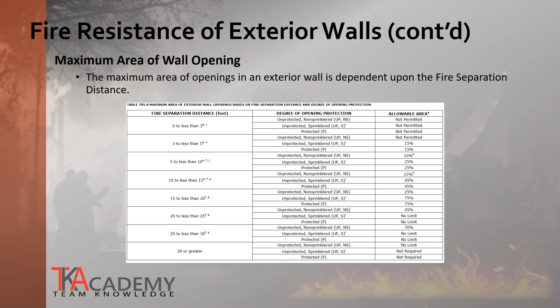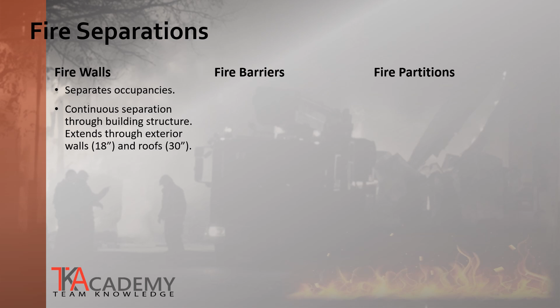Fire separations within a building are meant to contain a fire and keep it from spreading to other areas. Fire separations can be done with firewalls, fire barriers, and fire partitions. Firewalls are the most stringent, and they are used to separate occupancies. It is a continuous separation that extends through the building structure. Firewalls extend through exterior walls by 18 inches and through roofs by 30 inches.